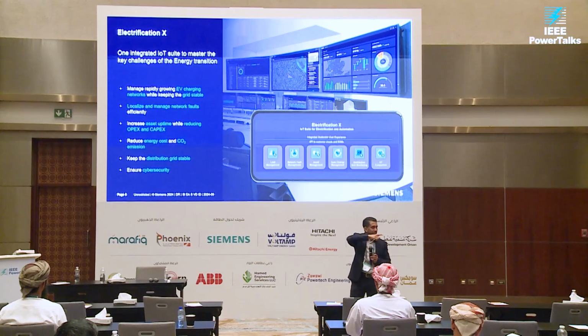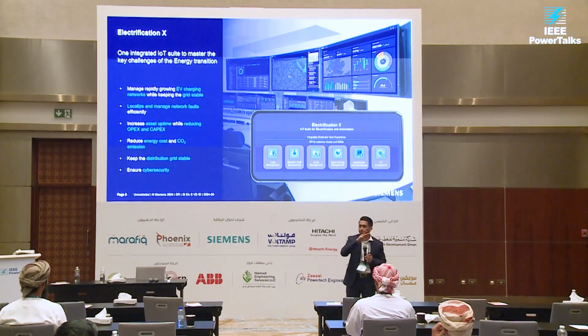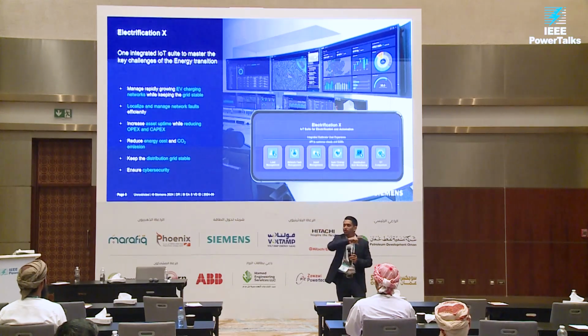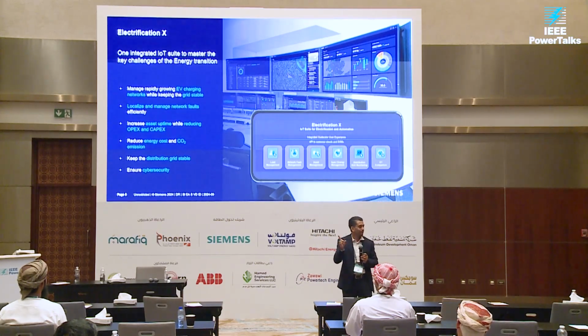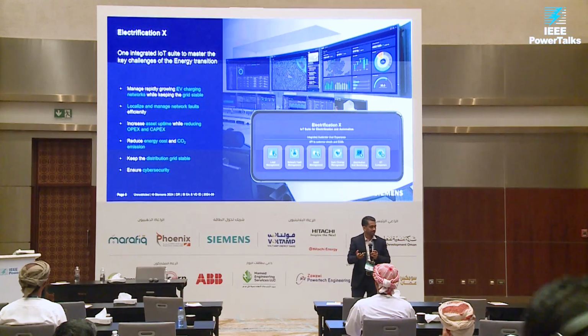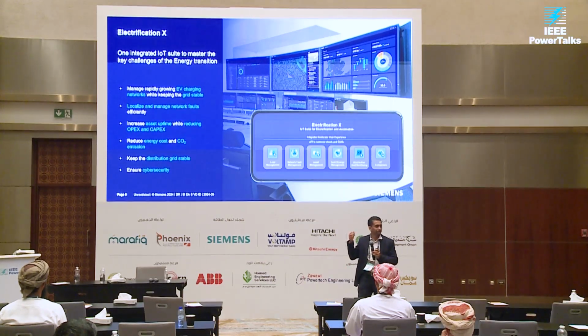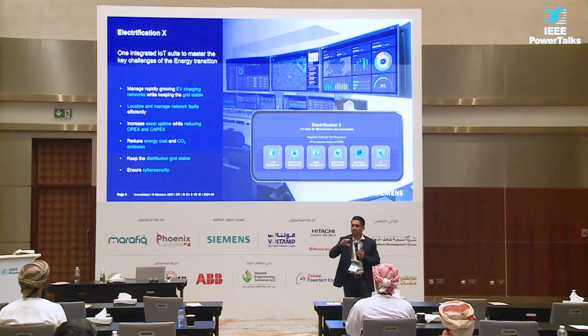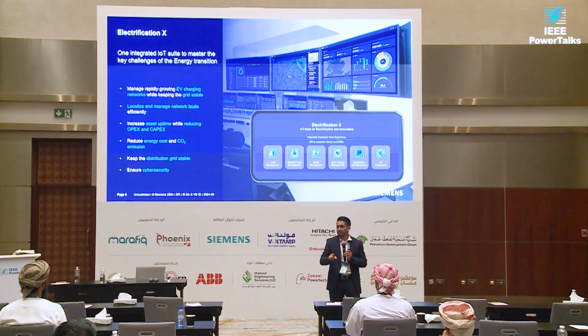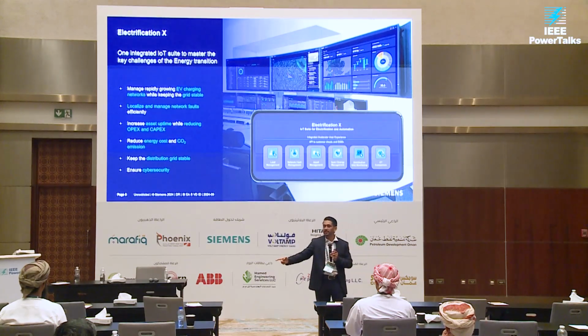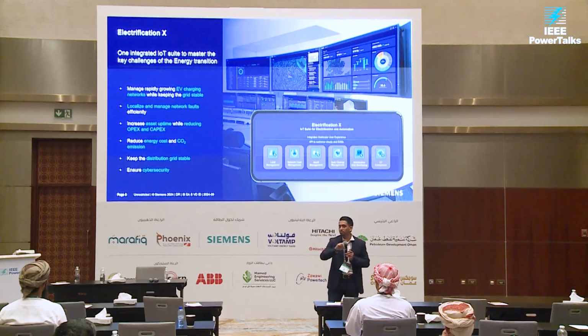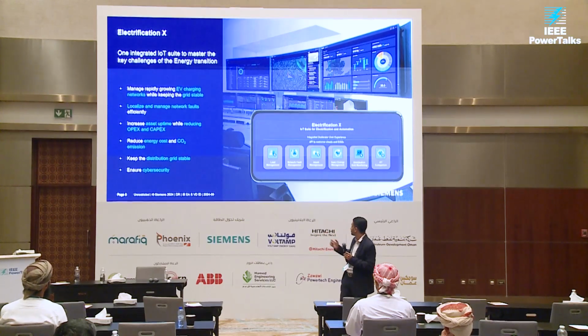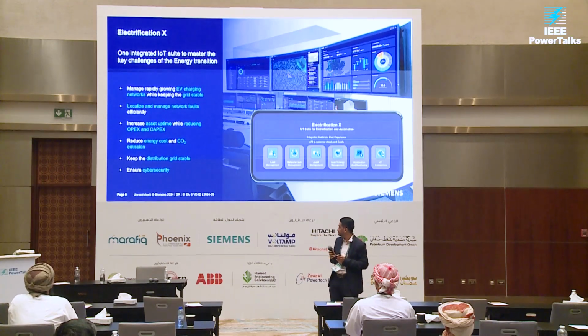This causes the primary station to trip. These two incidents are correlated. If I have a solution that can only monitor the overhead line but not the primary station, I won't be able to correlate that these two are due to the same reason. Unifying all these use cases into one single platform helps you see both faults on the same dashboard, so you can correlate immediately. The software itself will tell you that this line tripped at the same time the substation tripped, meaning they are correlated. This is the kind of benefit you get from unifying different use cases into one single platform.